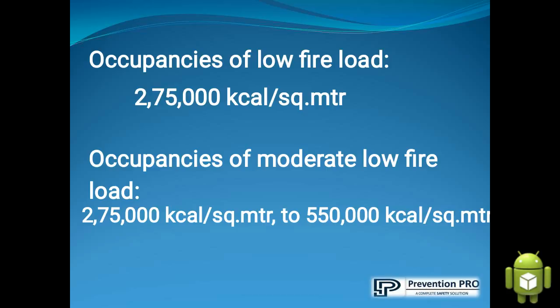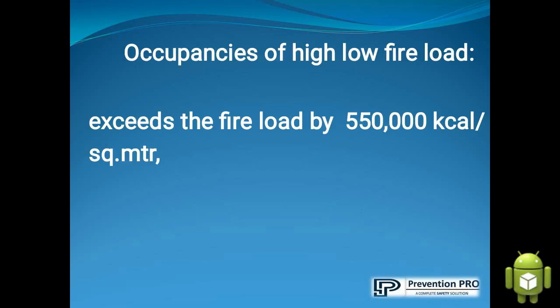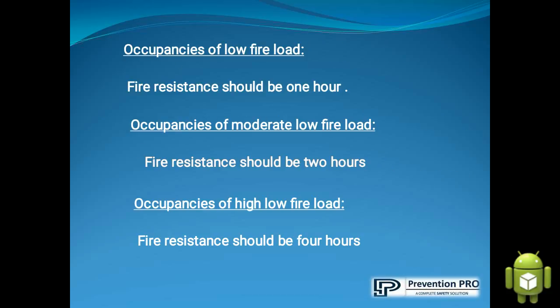Occupancies of low fire load is up to 2,75,000 kilocalories per square meter. Occupancies of moderate fire load is from 2,75,000 kilocalories per square meter to 5,50,000 kilocalories per square meter. Occupancies of high fire load exceeds 5,50,000 kilocalories per square meter. Low fire load: fire resistance should be one hour. Moderate fire load: fire resistance should be two hours. High fire load: fire resistance should be four hours.